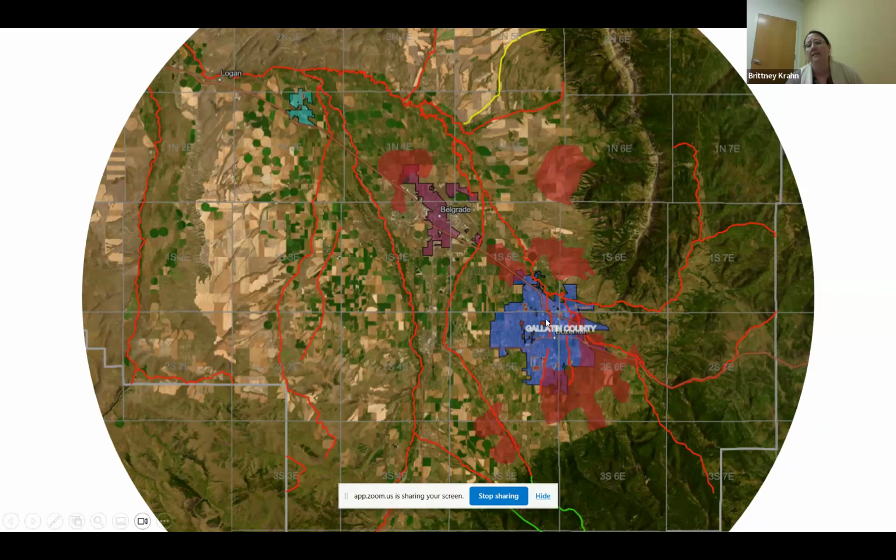City of Bozeman has a surface water discharge permit, where Belgrade has a groundwater discharge permit, and there are different parameters for the treatment styles that both need. The difference is that Belgrade needs more surface area of land to discharge, where Bozeman is a point source in terms of the discharge to the surface water itself, but their headworks and their pre-treatment has to take into account, it can happen in a smaller footprint, but those are way more expensive to put into place.